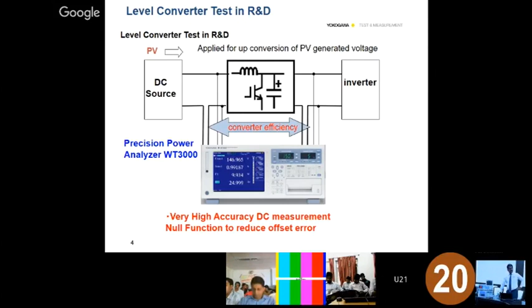For level converter testing in R&D applications: the photovoltaic side is DC coming from the solar panel, then it goes through a converter to the inverter. So what is the converter efficiency? We have the high accuracy WT3000 which can measure DC versus AC, or AC divided by DC, with 0.01% basic accuracy for highly accurate results.